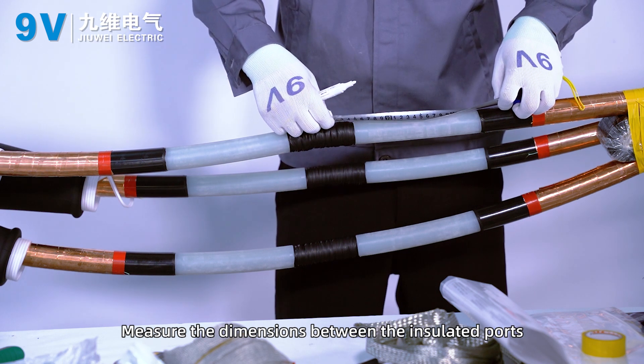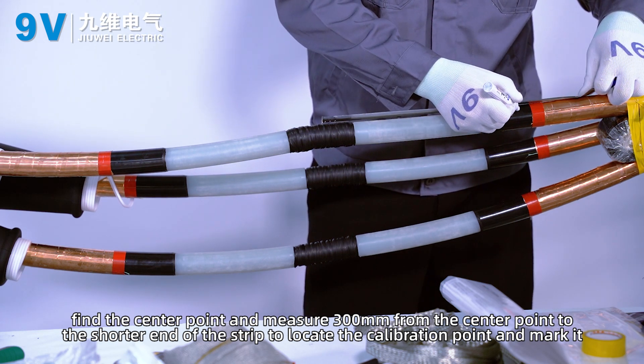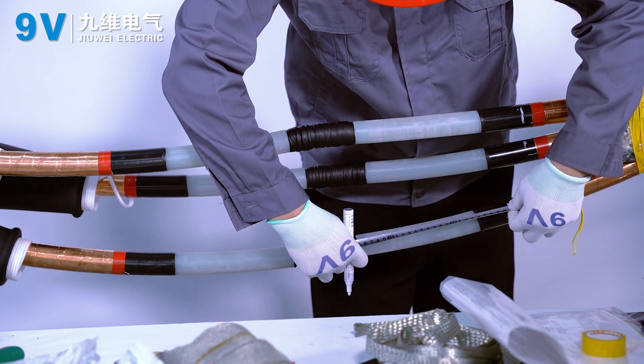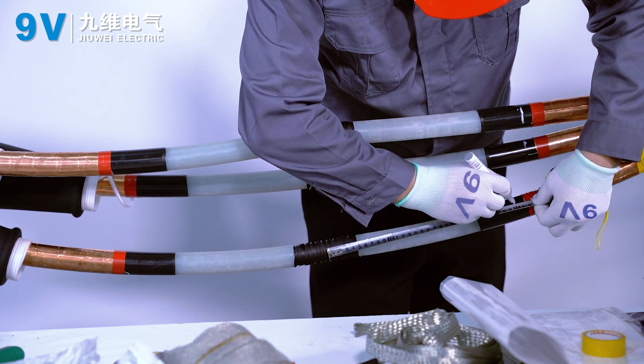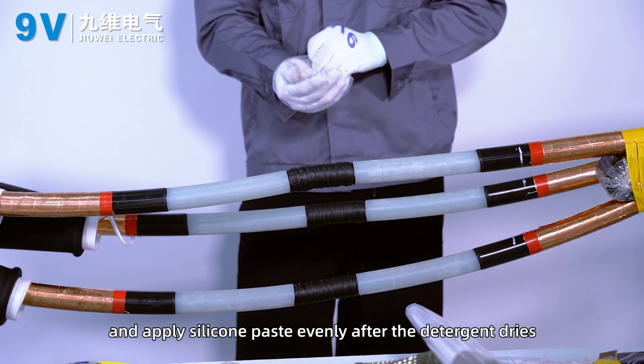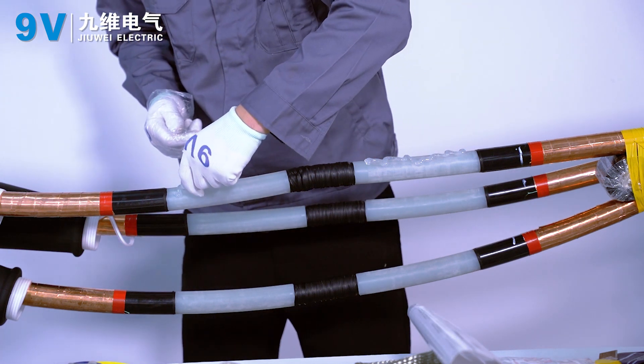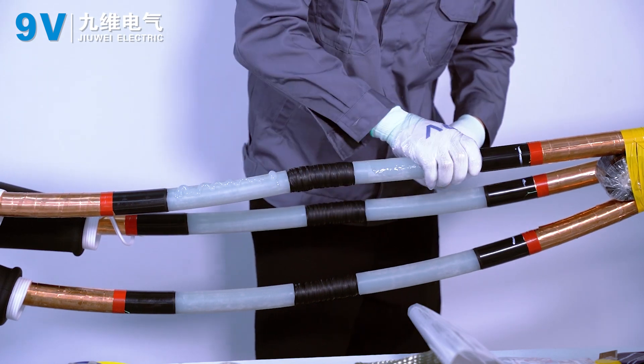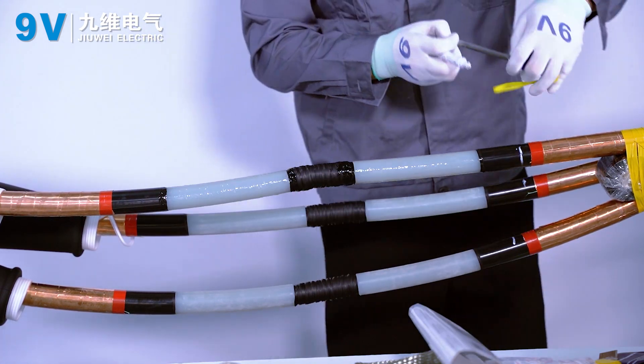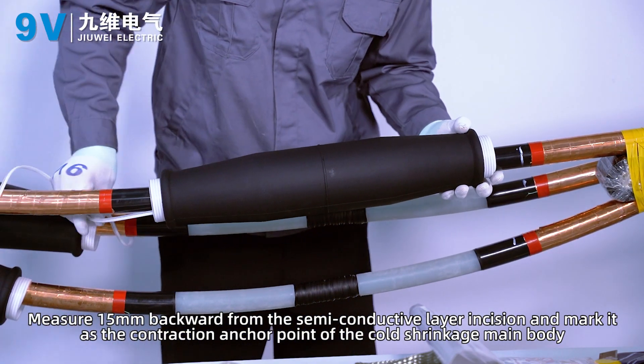Measure the dimensions between the insulated ports. Find the center point and measure 300 millimeters from the center point toward the shorter end of the strip to locate the calibration point and mark it. Install the cold shrink body. Clean the surface of the insulating layer with cleaning paper and apply silicone paste evenly after the detergent dries. Measure 15 millimeters backward from the semi-conductive layer incision and mark it as the contraction anchor point of the cold shrinkage main body.